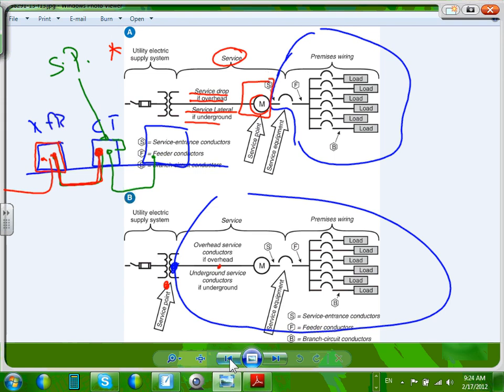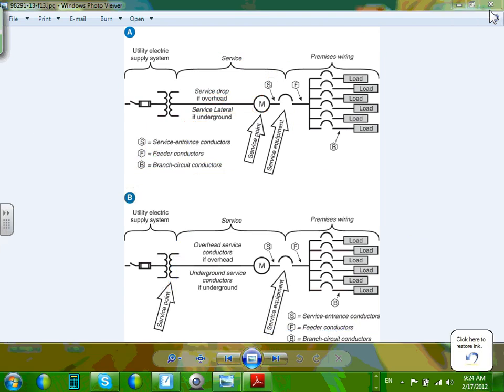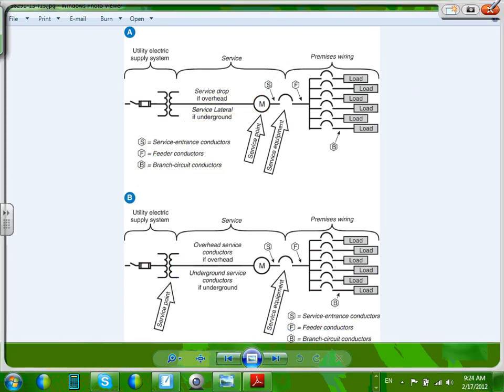Let me take a snapshot of that. Okay, based on where you decided, it becomes a feeder, can you guys see the F? Right here is a feeder, and right here is a feeder. Service conductors, let's just use blue. This is a service conductor, so you own and operate it. This is a service conductor here. You own and operate it. And of course, these ones here are branch circuits. Any comments, any questions about the service point? What's the service point? The point where your responsibility stops or starts, or the electrical utility's responsibility stops or starts.